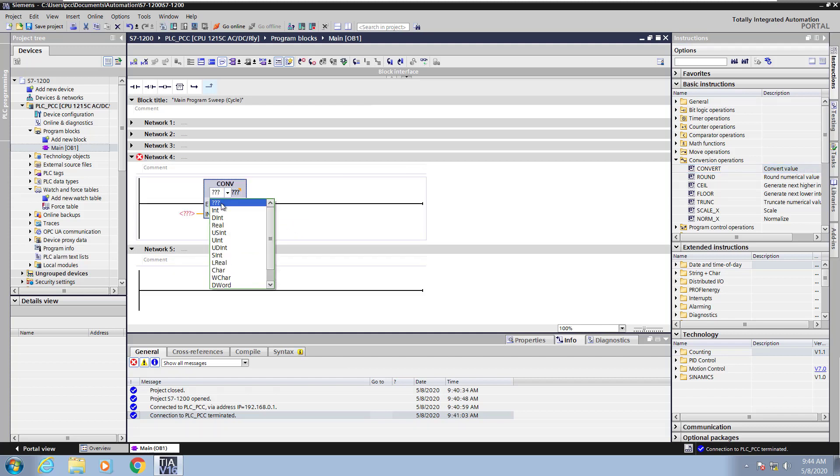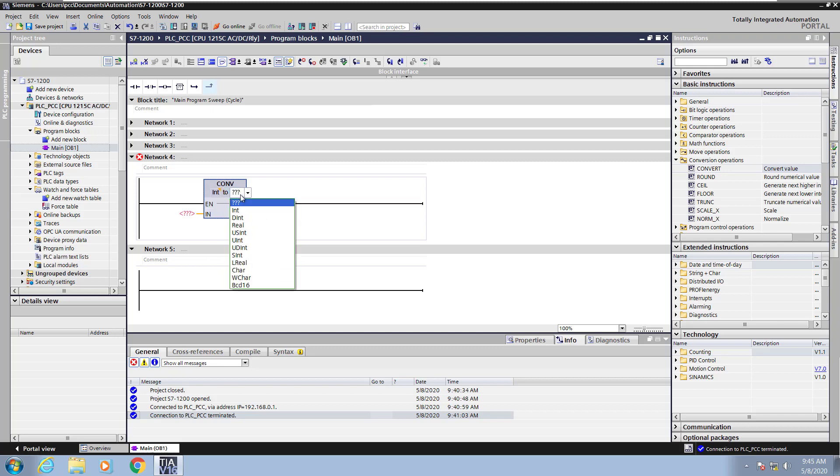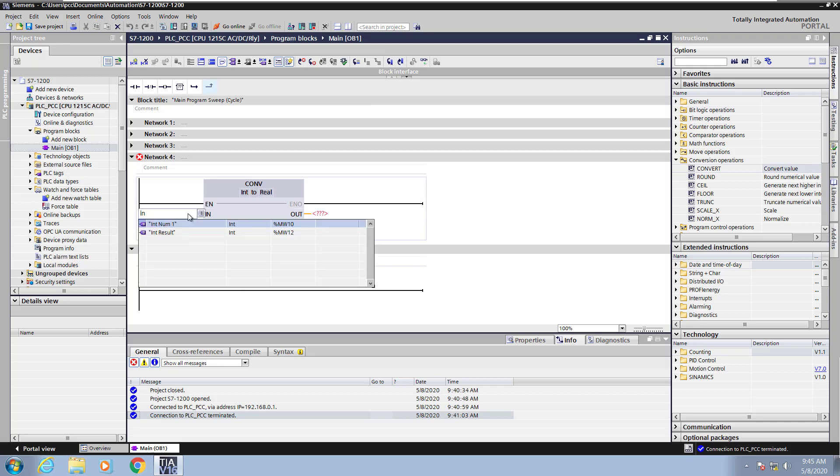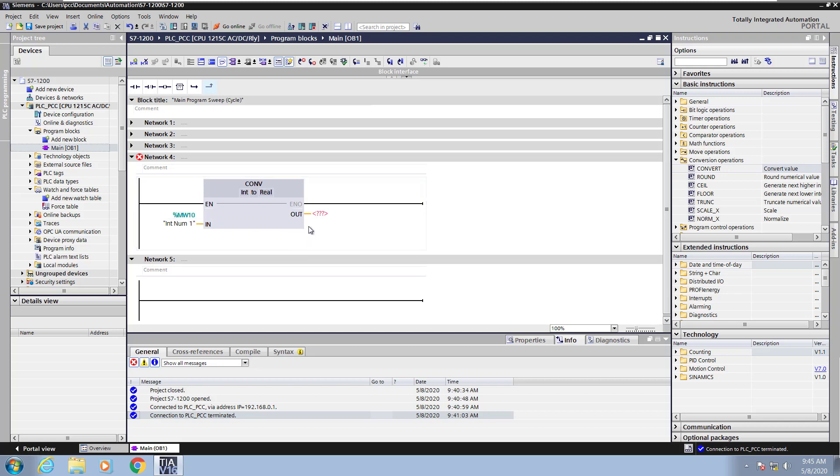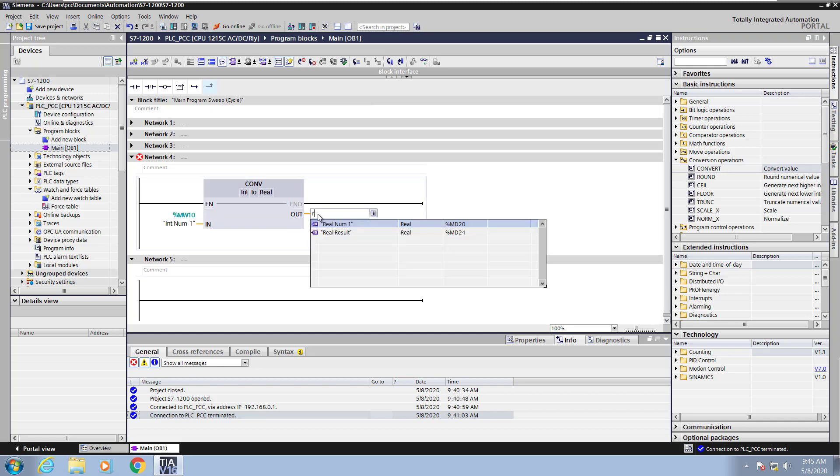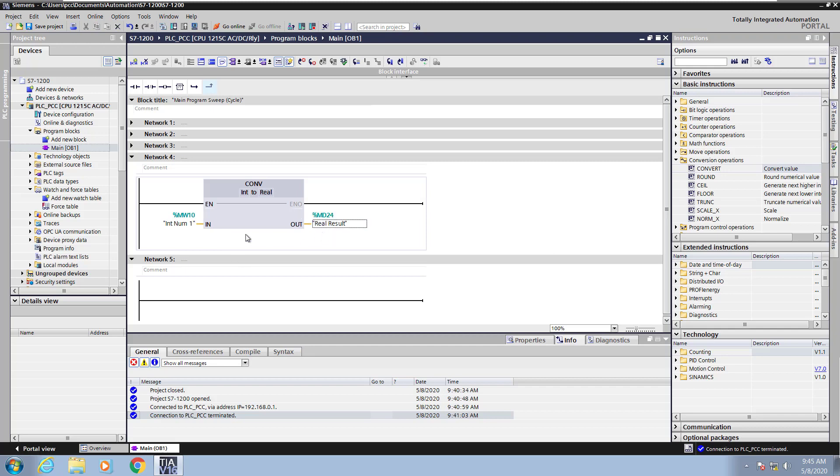This allows you to convert from one data type to another, so I'm going to go from an integer to a real value. On the input side, I'm going to enter in an integer tag, so I'll just start typing the first few letters of the tag. On the output side, I am going to select a real tag, so I'll start typing like R, and that will bring in a tag that starts with the letter R. So I'm going to convert an integer to a real.